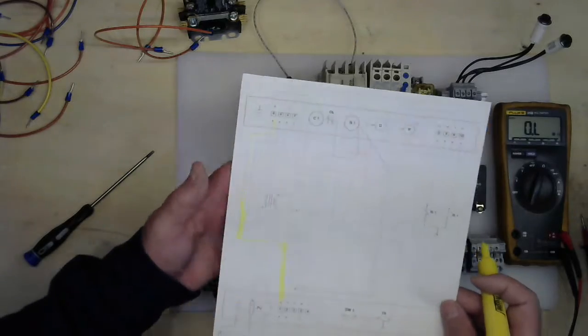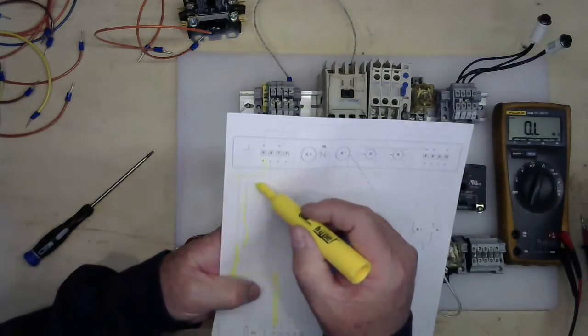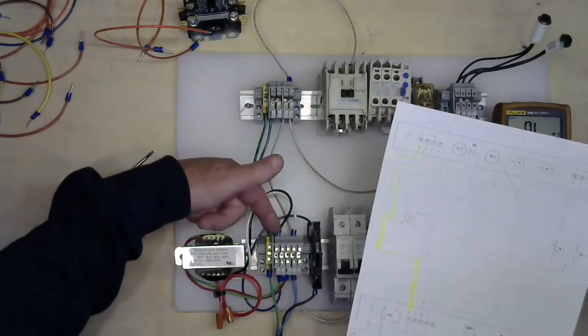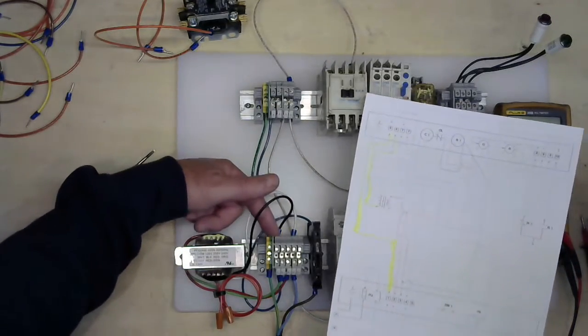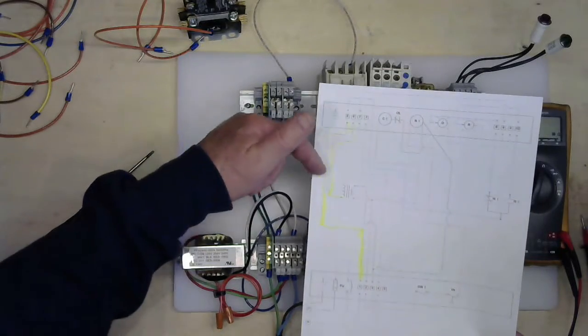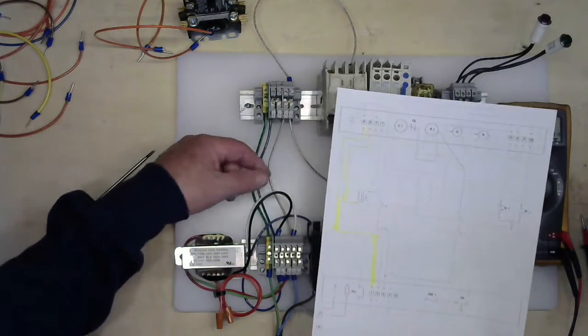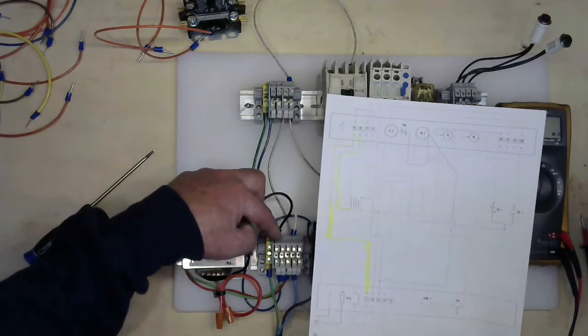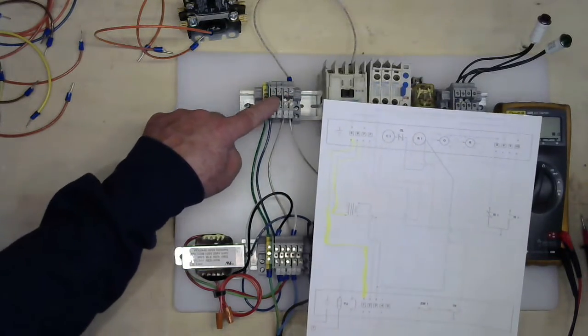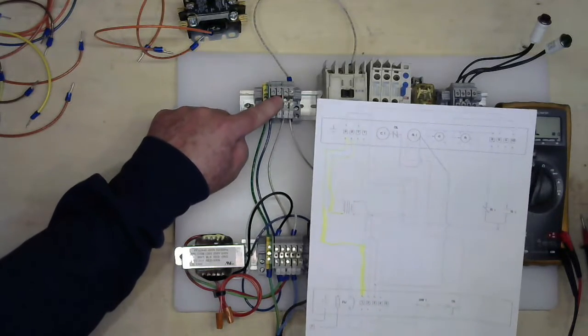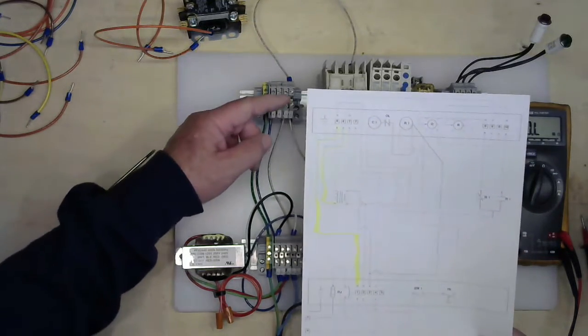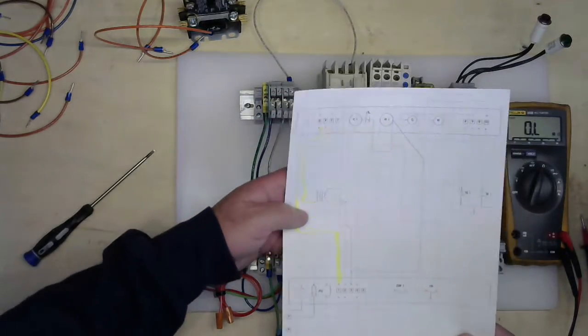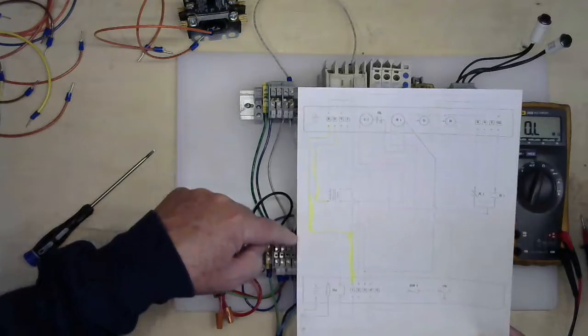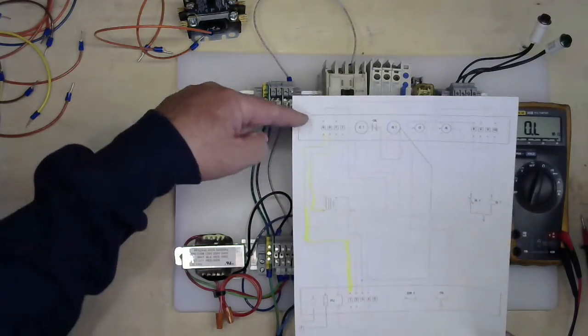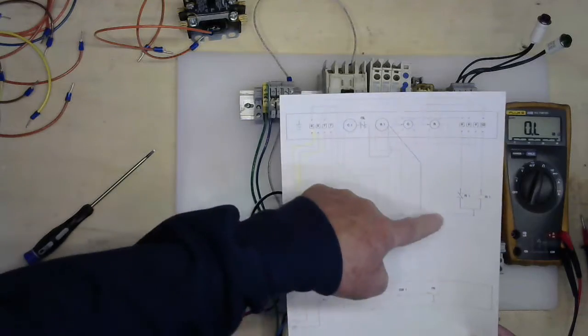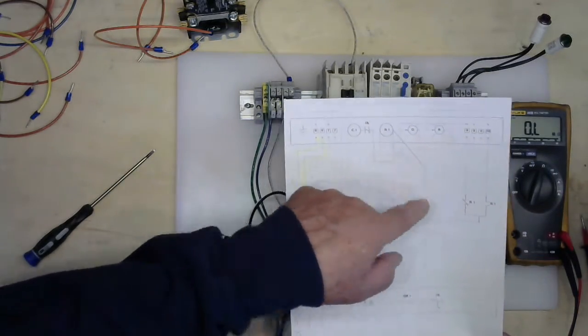And my wire 6 is already connected to our transformer. Even though it's not connected to 6 up here, we have it double lugged on 1. So, small technicality as far as the description goes. It was easier to put the wiring down here than it is back up there, because on the future diagrams we're going to be using terminal 6 more in either room. So, what we can do, now that we already have the transformer connected, is we don't need to do any additional wiring here. We can go from terminal 6, follow it around to the common of our 24 volt relay.